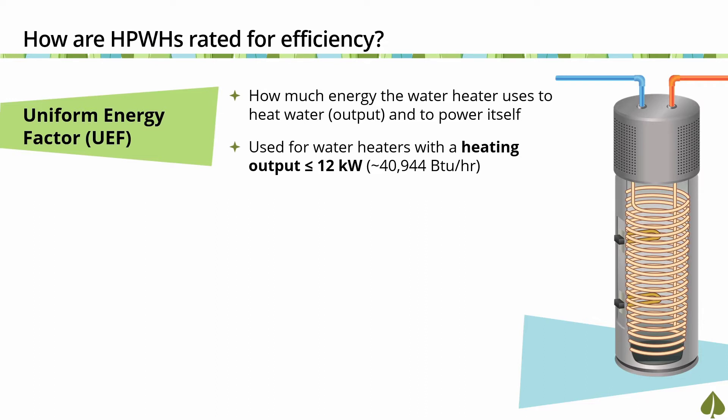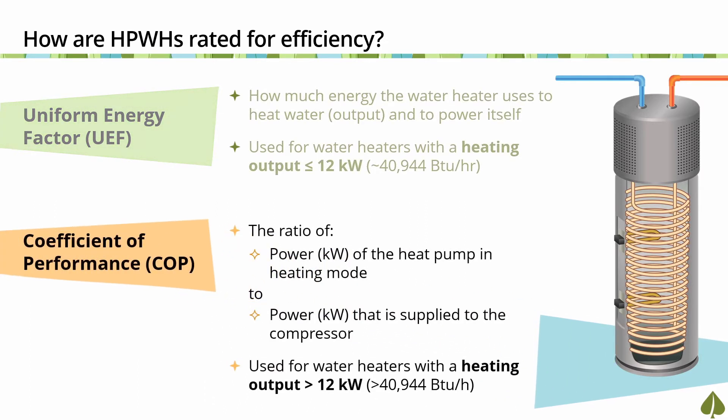The second metric is Coefficient of Performance, or COP. COP is a measure of a heat pump's efficiency and indicates the ratio of power in kilowatts of the heat pump in heating mode, or in cooling mode, to the power in kilowatts that is supplied to the compressor. COP is the metric used for water heaters with a heating output greater than 12 kW, or 12,000 watts. The higher the COP, the more efficient the heat pump.